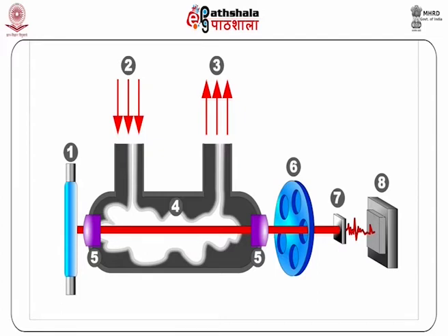The spinning filter wheel contains several narrow filters which are specific for the wavelengths of those bonds that are present in ethanol. A photocell detects the light crossing each filter and converts it to an electrical pulse. This electrical pulse is then directed towards a microprocessor which interprets the pulse for calculating the BAC on the basis of IR absorption.